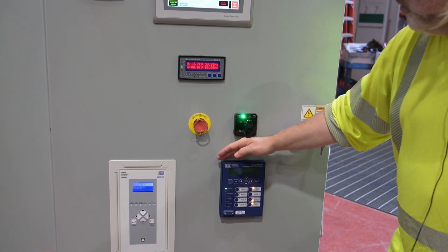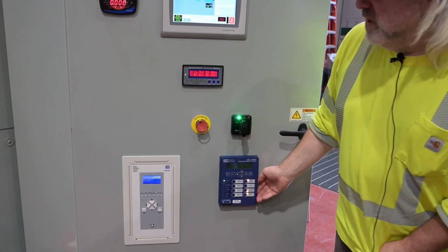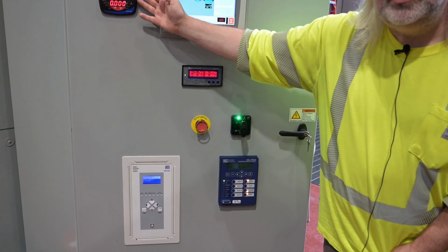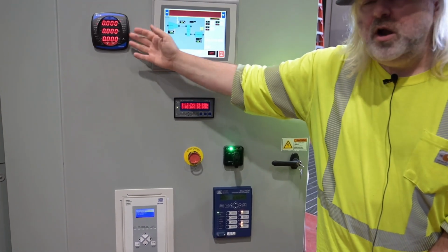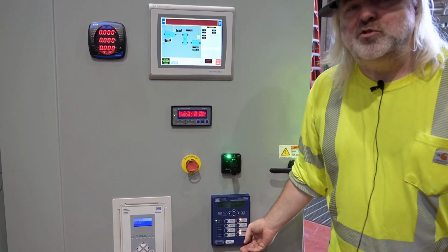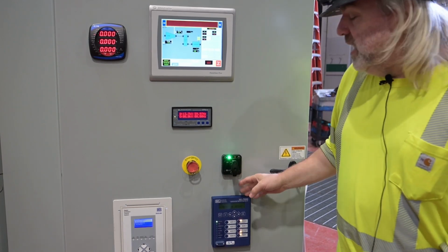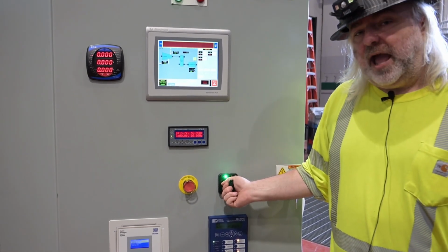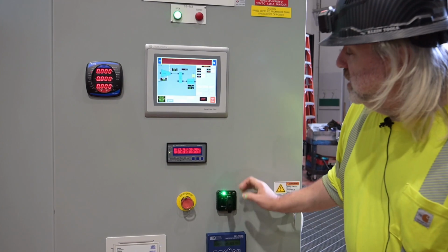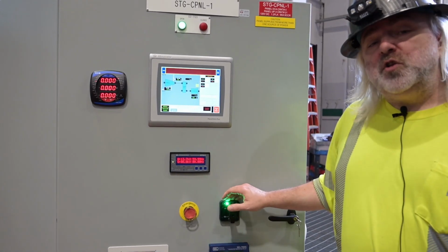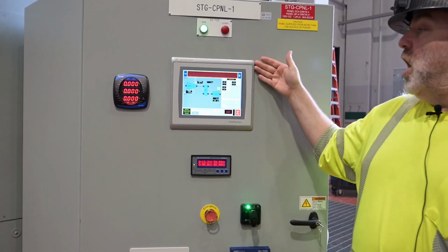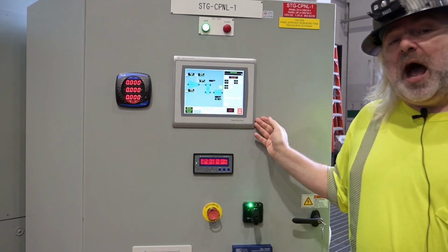Again, underneath, we have our generator protection relay. This relay is monitoring our voltage, our frequency, our current, and our power, and deciding if we're outside boundary. If we're outside boundary, it will issue a trip to the lockout relay. So, those are the components on the doors. The last component is our human machine interface, our HMI.